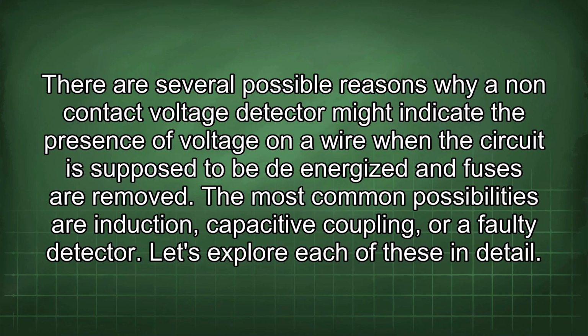There are several possible reasons why a non-contact voltage detector might indicate the presence of voltage on a wire when the circuit is supposed to be de-energized and fuses are removed. The most common possibilities are induction, capacitive coupling, or a faulty detector. Let's explore each of these in detail.